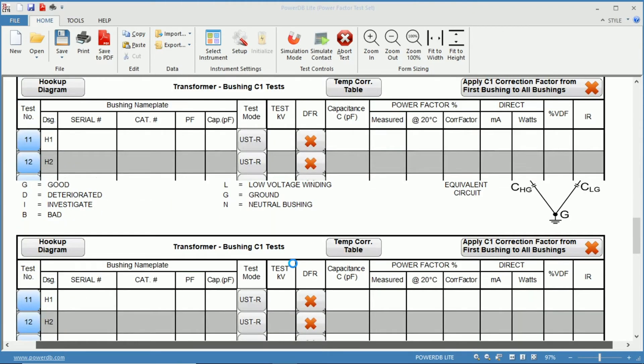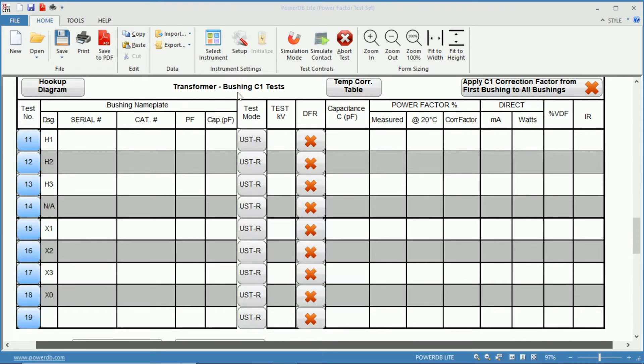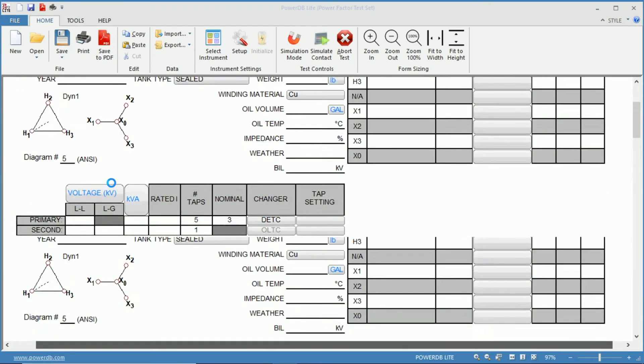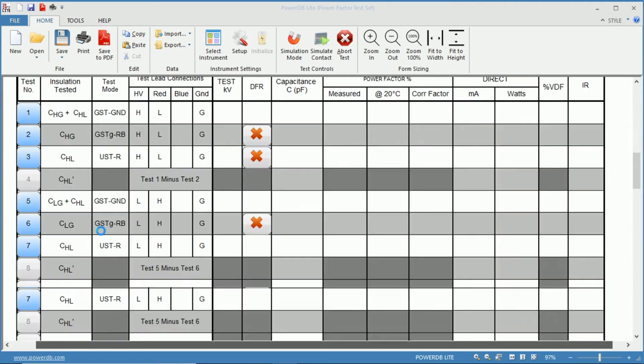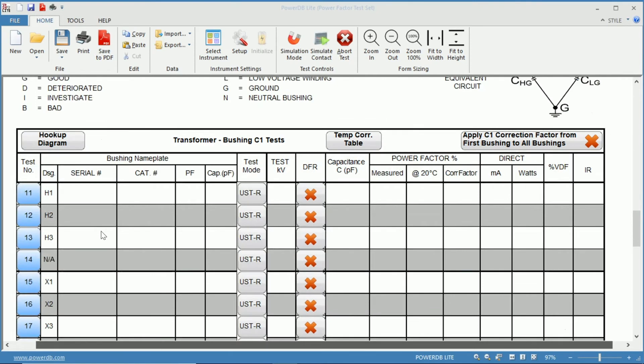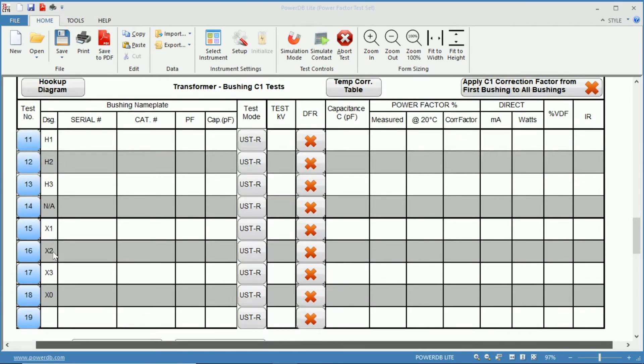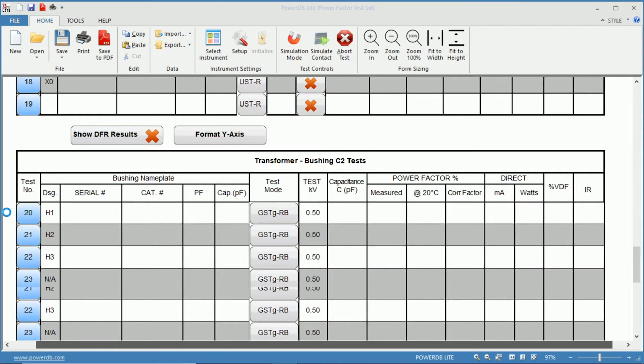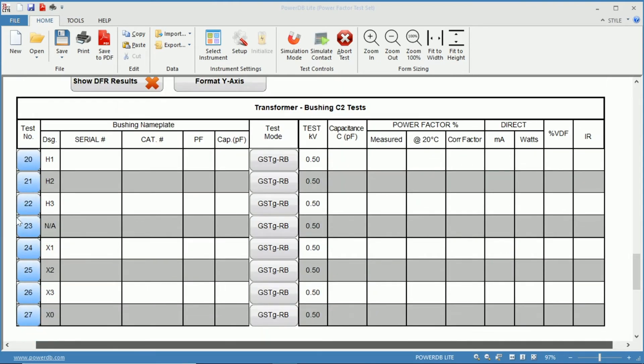Now down below we have our C1 Bushing tests, and because we are in a Delta Y vector diagram, we have H1, H2, and H3, X1, X2, X3, and X0. Since there is no neutral on the Delta, we have no tests to be performed there. And the same can be said with the C2 test as well.